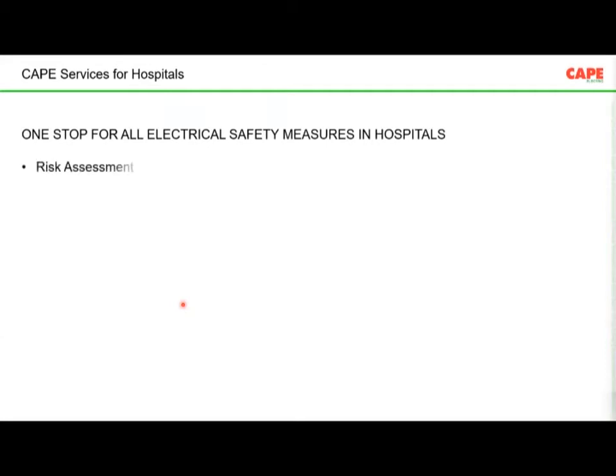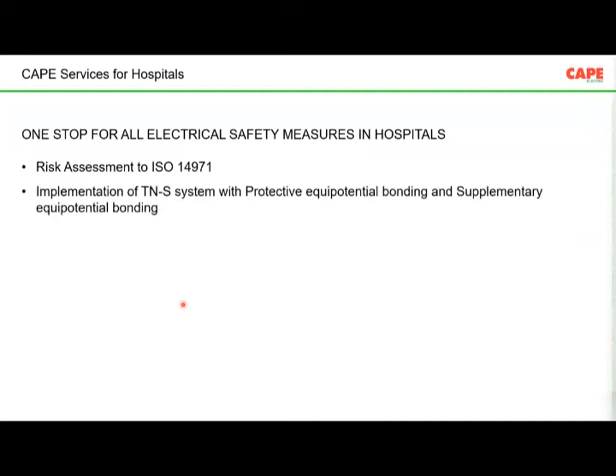Now, what we offer in CAPE, we are capable of offering the entire solution, starting with the risk assessment as per ISO 14971. In medical areas, there are chemical things, biomedical things, wastes, how to handle them, and in case of accidents, how to solve the issues, which are included in the ISO. In this particular ISO, you have to make a risk assessment. Then, implementation of TNS system with protective equipotential bonding and supplementary equipotential bonding. This we are doing already in several hospitals.